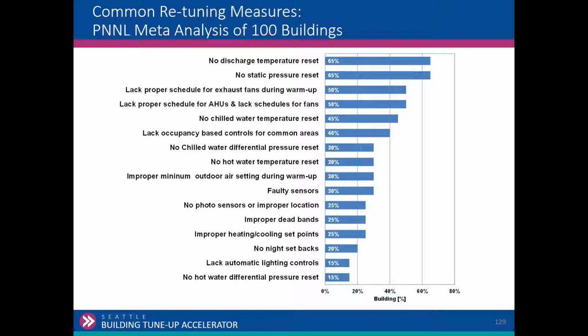Lack of proper scheduling, and lack of schedules for fans. So that's one of the primary assessment elements: to just verify scheduling of the major equipment and systems. If you look at a lot of these buildings, office buildings especially, they're only occupied about 3,000 hours a year. So for 5,000 hours a year, they're unoccupied. So how much energy can we save when they're unoccupied, which doesn't affect anybody's comfort and extends the life of the equipment.